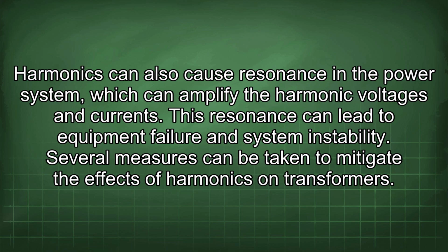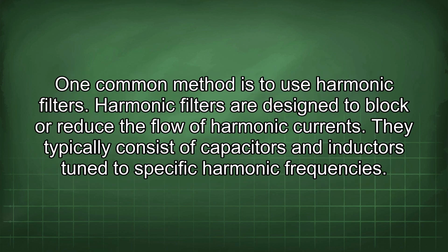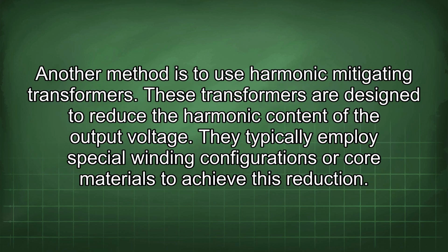Several measures can be taken to mitigate the effects of harmonics on transformers. One common method is to use harmonic filters. Harmonic filters are designed to block or reduce the flow of harmonic currents. They typically consist of capacitors and inductors tuned to specific harmonic frequencies. Another method is to use harmonic mitigating transformers. These transformers are designed to reduce the harmonic content of the output voltage. They typically employ special winding configurations or core materials to achieve this reduction.